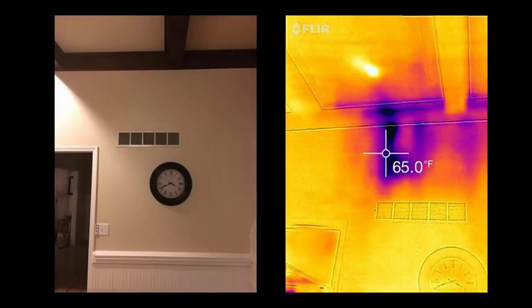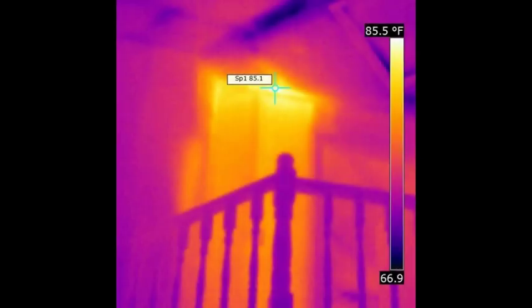Here's a wintertime example in a basement-style house in Kansas City. The purple pattern is from cold air chilling the backside of the drywall as it is being sucked down from the attic. Here's an example of what you might see if the return wall cavity is wide open to a hot attic. Now, since the attic air has to be hotter or colder than the house air for a color change to occur, the results depend on the outdoor conditions and time of day. You could have leakage, but thermal imaging wouldn't necessarily show it at the time of your inspection.